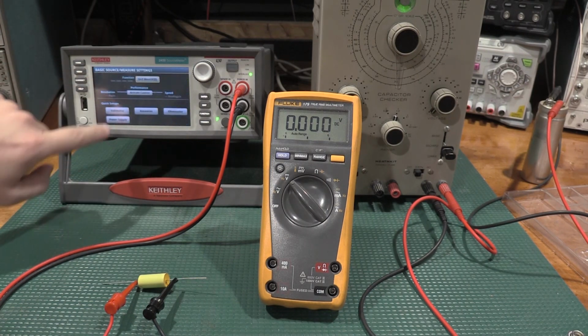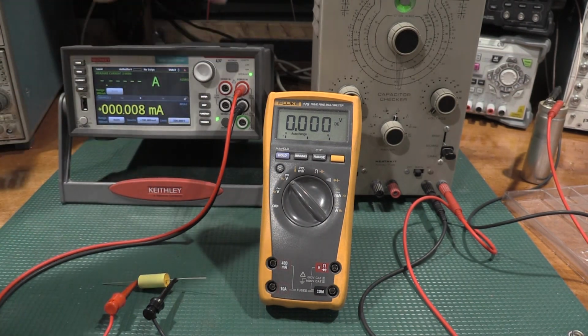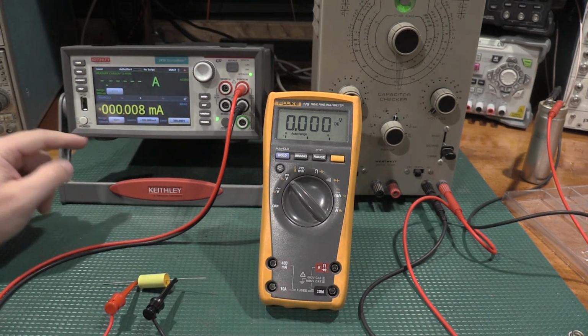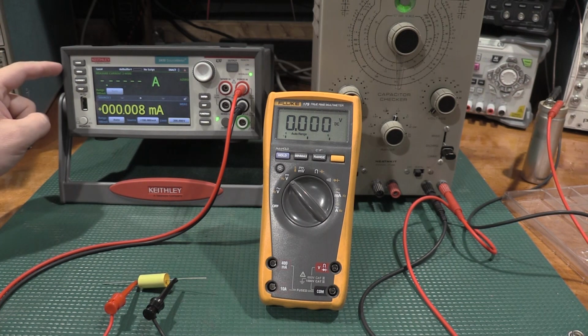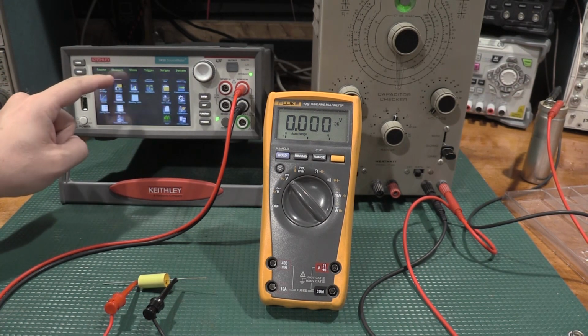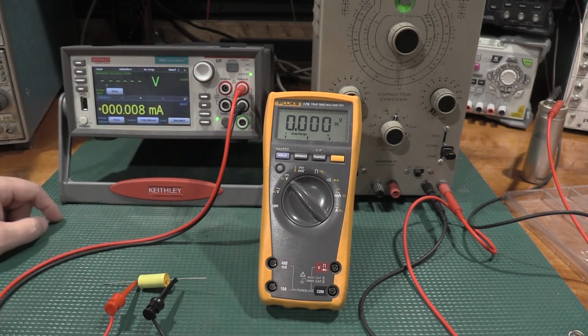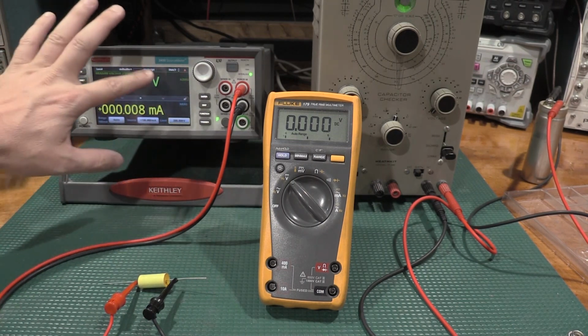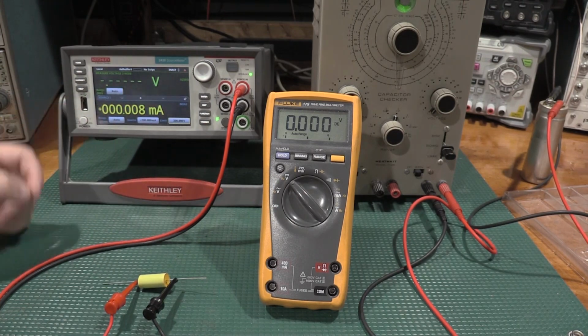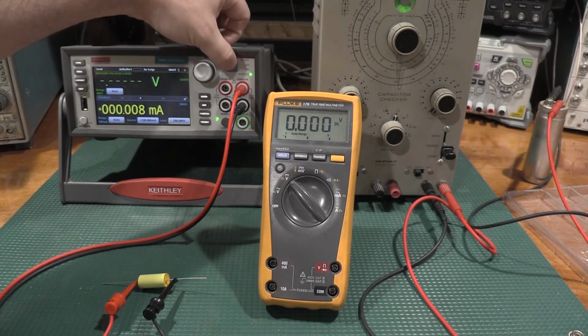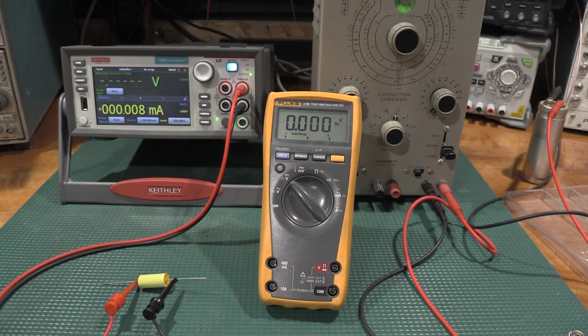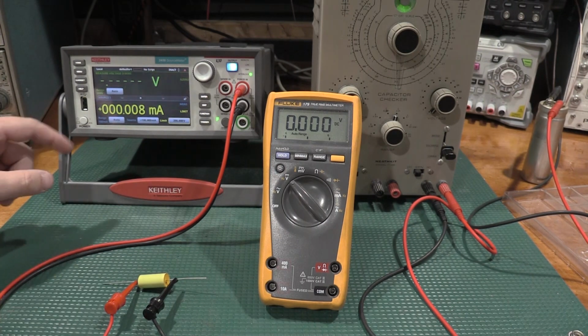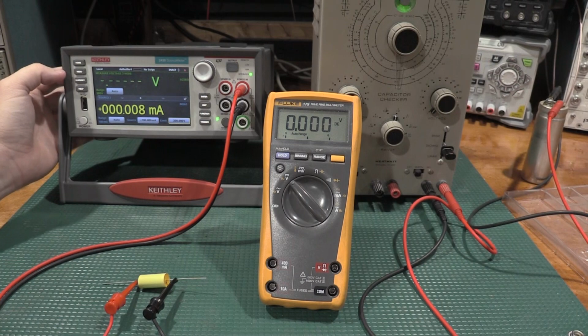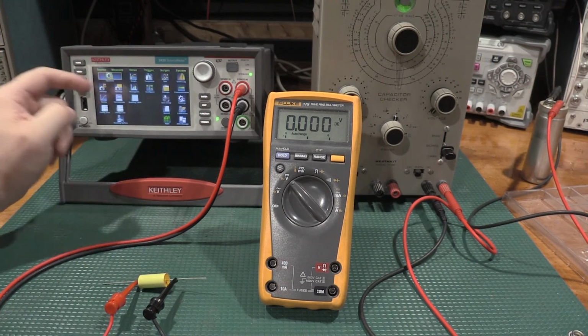And what we'll do is we'll source voltage and measure current. And I'm at 200 volts. Or no, I'm sorry. We will source current and measure voltage. So we're sourcing current through the capacitor, measuring the voltage. If it limits out at 200 volts, we'll see what the current is across this capacitor at 200 volts. All right, that didn't work because we never got to 100 milliamps.